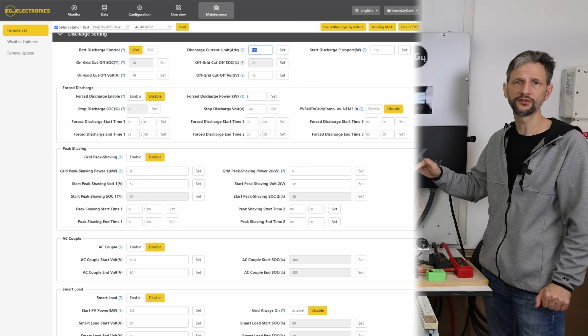For the discharge setting, I'll once again use voltage instead of state of charge to set the discharge current limit to 162 amps for this inverter. Now these can put out 200 amps. If I had a 10,000 watt inverter, I could set it a little bit higher.